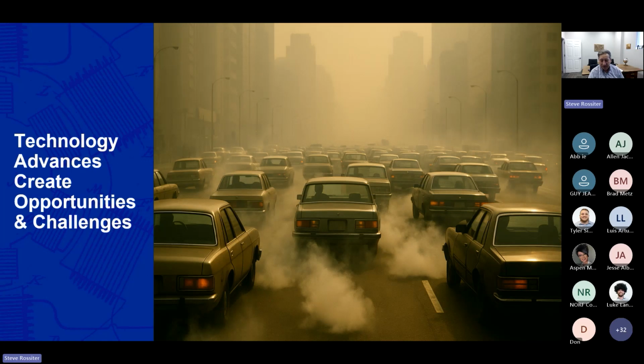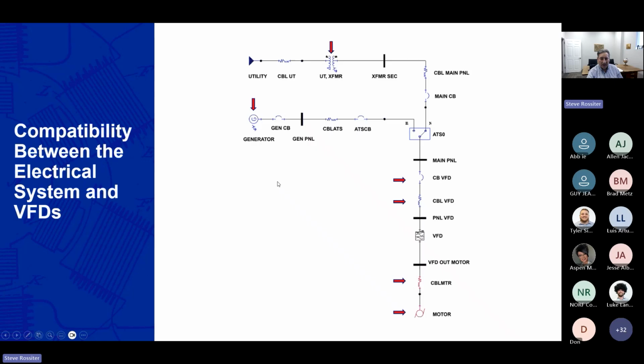There's now a very different consequence associated with having non-sinusoidal waveforms going through transformers and breakers and transmission lines and protective devices. So I want to bring up a typical one line of a modern electrical system, and point out where many of these challenges may now occur because of this little variable frequency drive right here. And I need to remember, the reason we're putting up with all of this is because of the phenomenal benefits of the variable frequency drive, like the energy efficiency, the improvement on the drivetrain wear and tear, and even the protective technologies is so much greater than ever before in being able to shut down a faulted device.